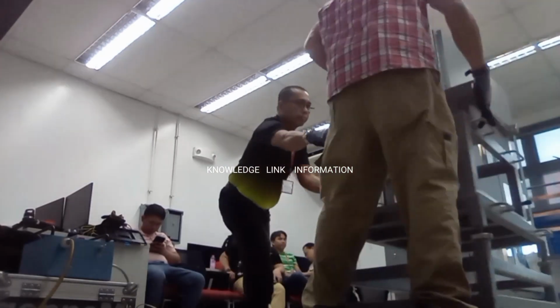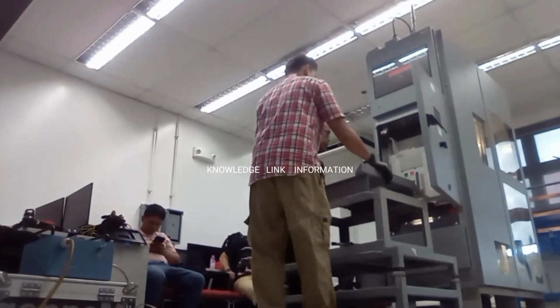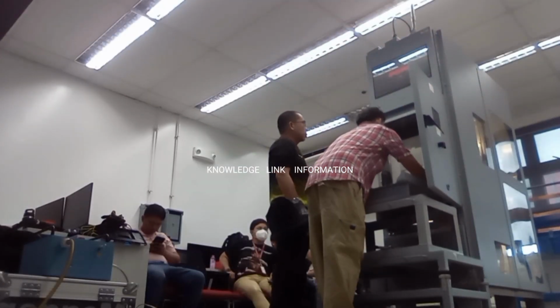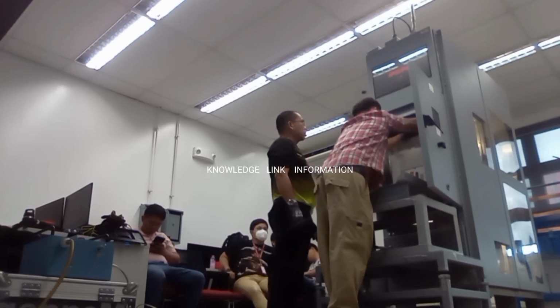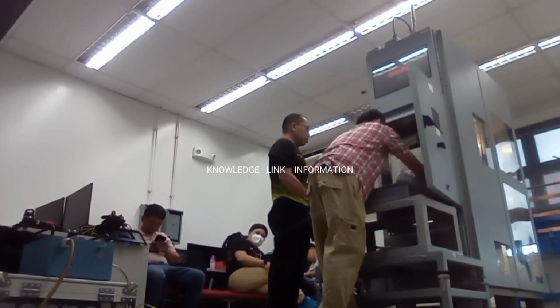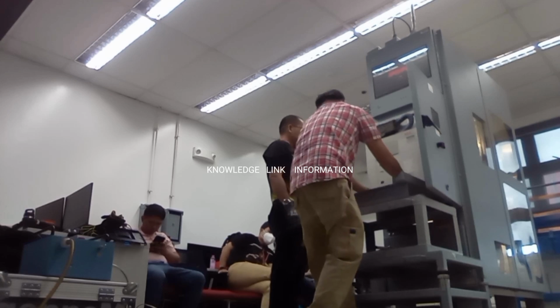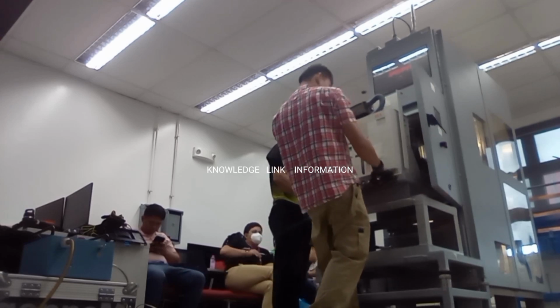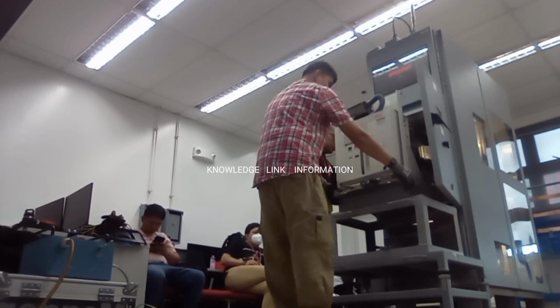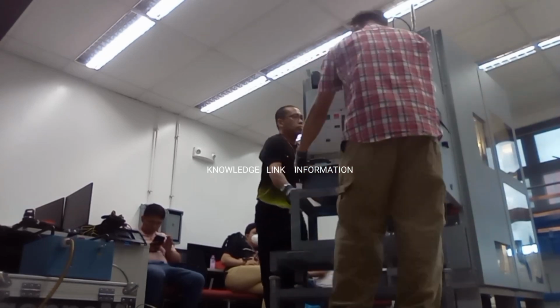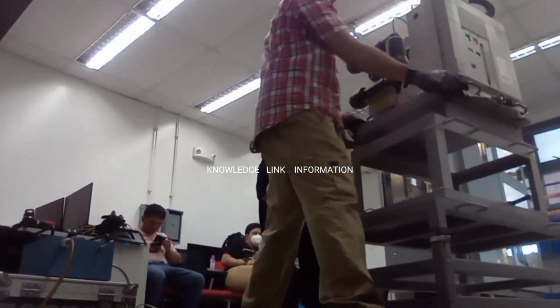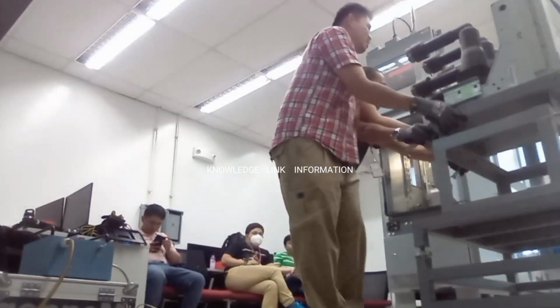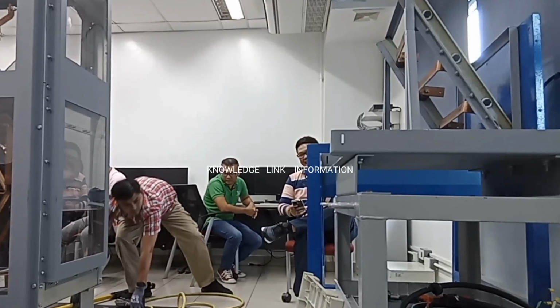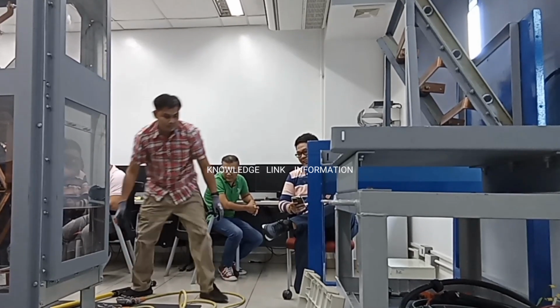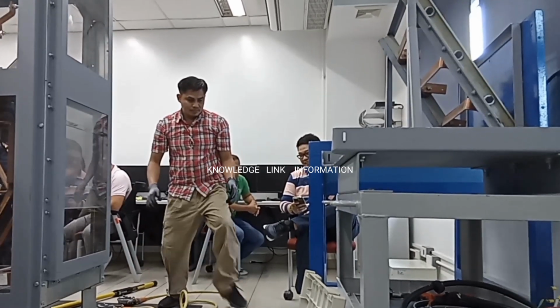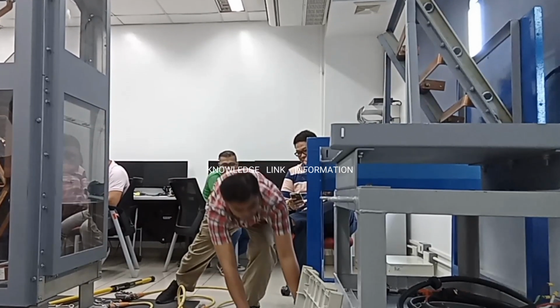Number 7. Put the trolley in position to load the high-voltage circuit breaker, and disconnect the breaker control line plug from the switchboard socket. Number 8. Unlock the high-voltage breaker and pull it out onto the trolley for better isolation from the switchboard. Number 9. Move the trolley away from the switchboard for job preparation, to keep the high-voltage breaker safe from damage. Number 10. Go to the bus bar behind the switchboard panel, and make a bus bar earthing for more safety on the job to be done.